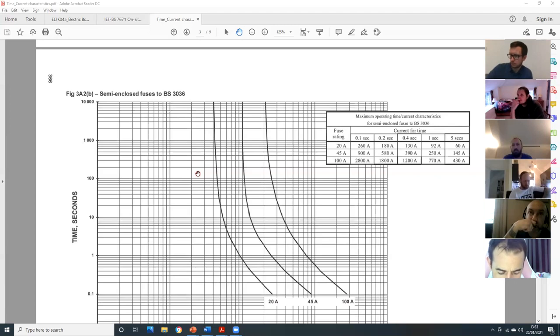So you now have got to make sure you put typically a 20 amp or 15 amp fuse to protect that cable. Okay, so in summary, because we've got about 5 minutes left: fusing factor is an historic term, because it comes from the old days of fuses, but it does apply to all overcurrent protective devices.